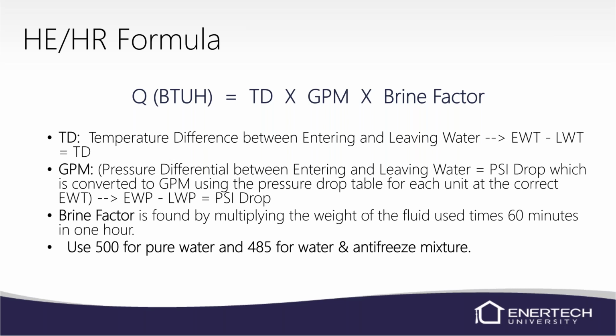On that brazed plate, you've got a water plate, refrigerant, water, refrigerant, water, refrigerant. So if one of them breaches, you get water in the refrigerant circuit and the compressor's toast, the unit's trashed. So make sure that if you think that it could freeze, you're putting antifreeze in it.